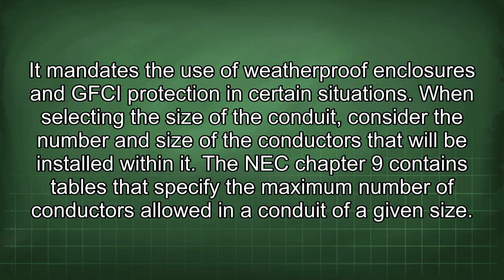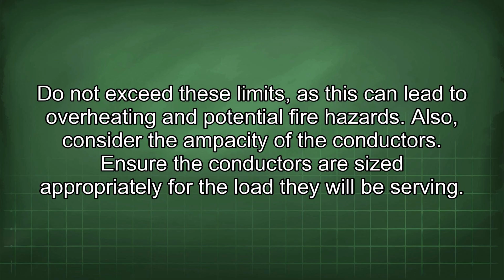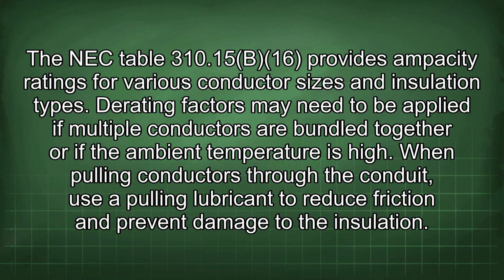When selecting the size of the conduit, consider the number and size of the conductors that will be installed within it. The NEC Chapter 9 contains tables that specify the maximum number of conductors allowed in a conduit of a given size. Do not exceed these limits, as this can lead to overheating and potential fire hazards. Also, consider the ampacity of the conductors. Ensure the conductors are sized appropriately for the load they will be serving. The NEC Table 310.15(B)(16) provides ampacity ratings for various conductor sizes and insulation types. Derating factors may need to be applied if multiple conductors are bundled together or if the ambient temperature is high.